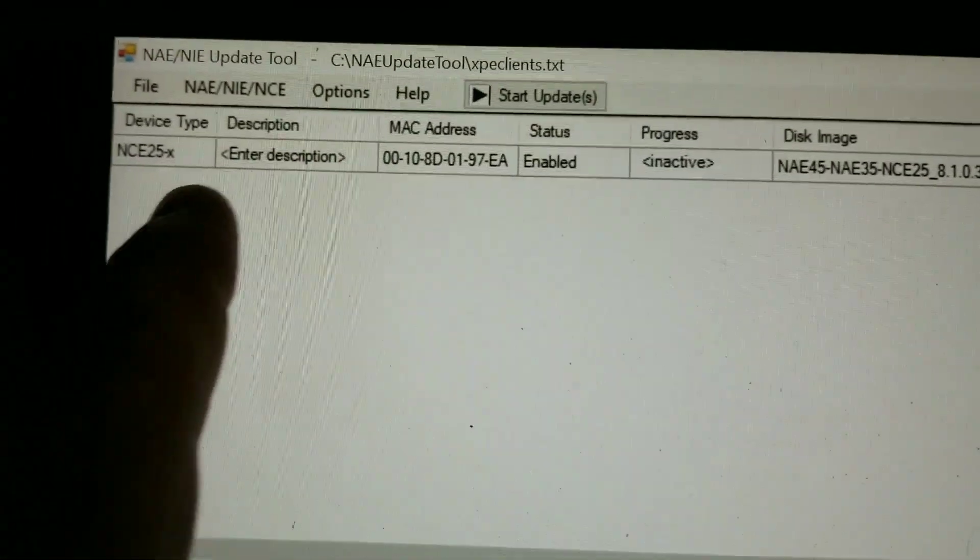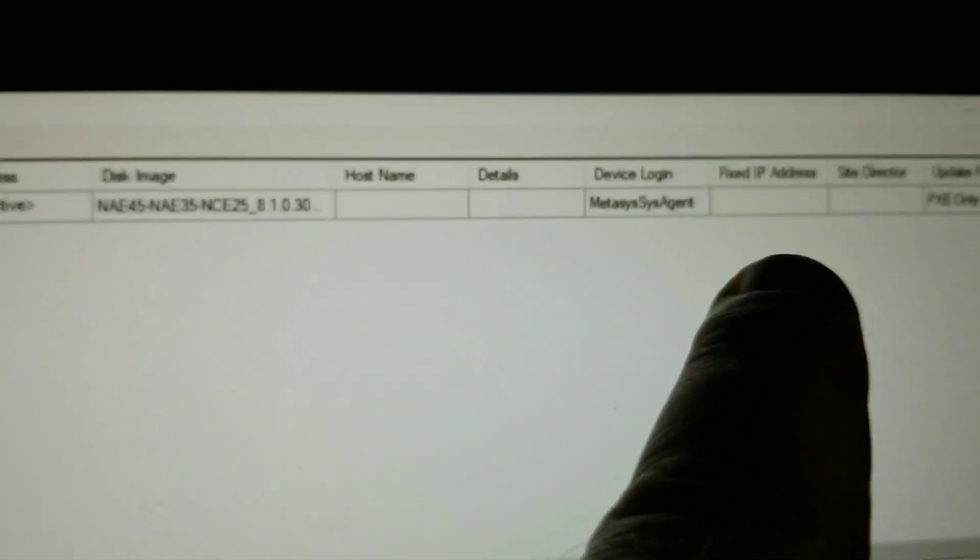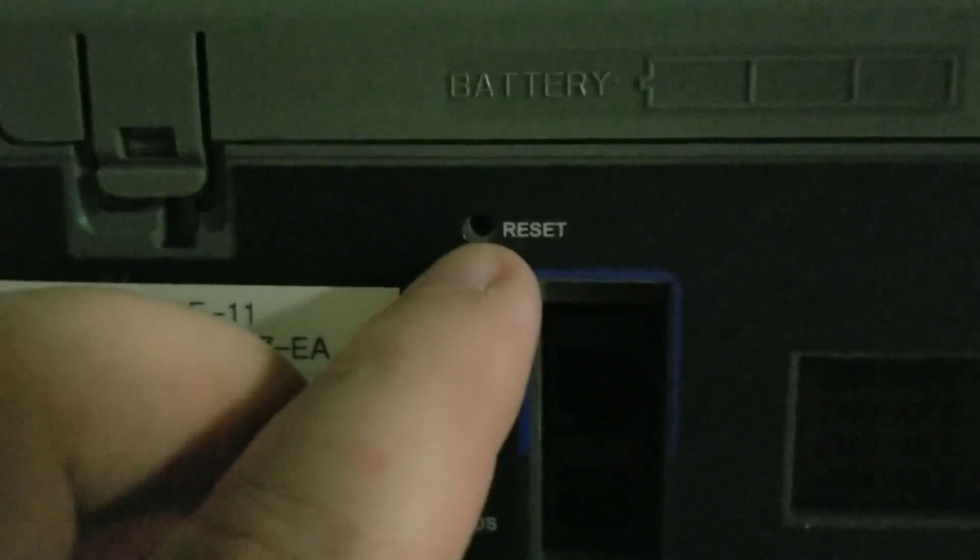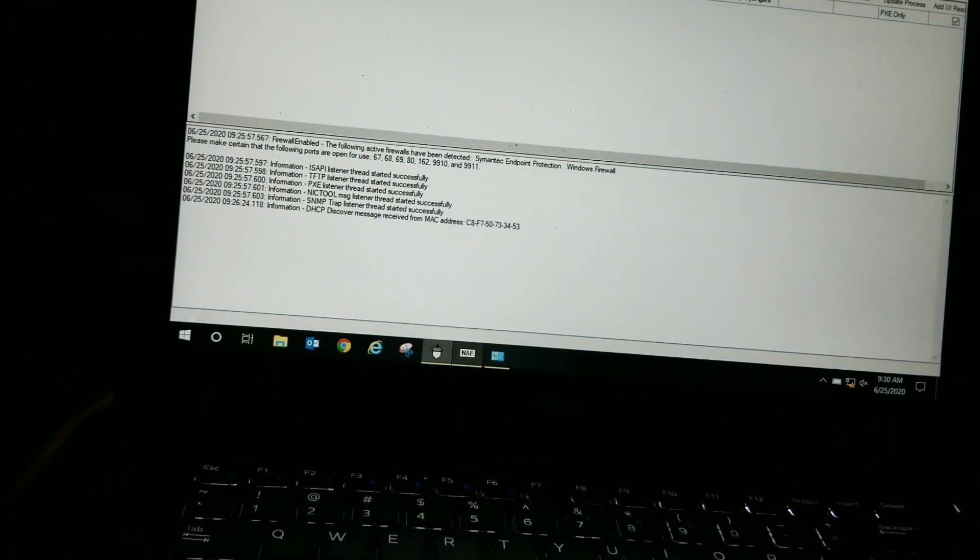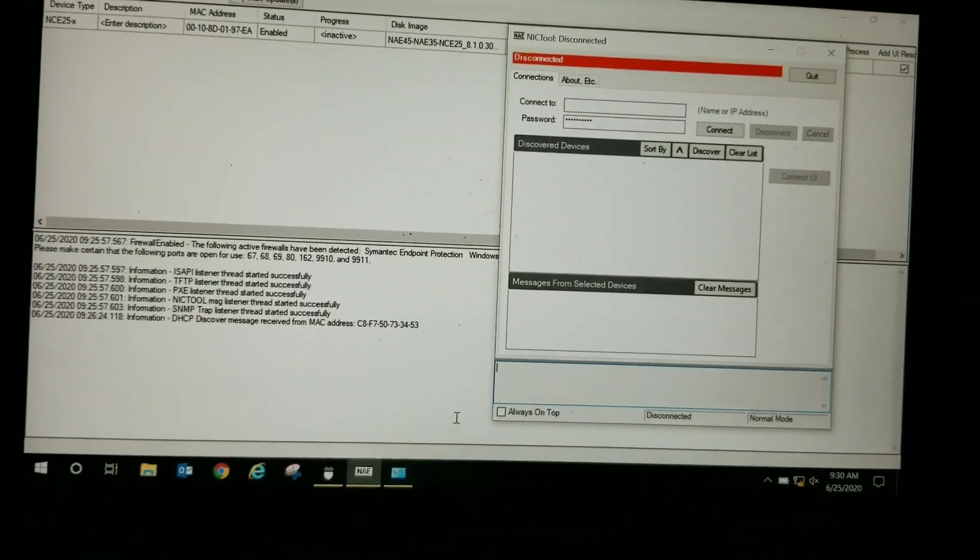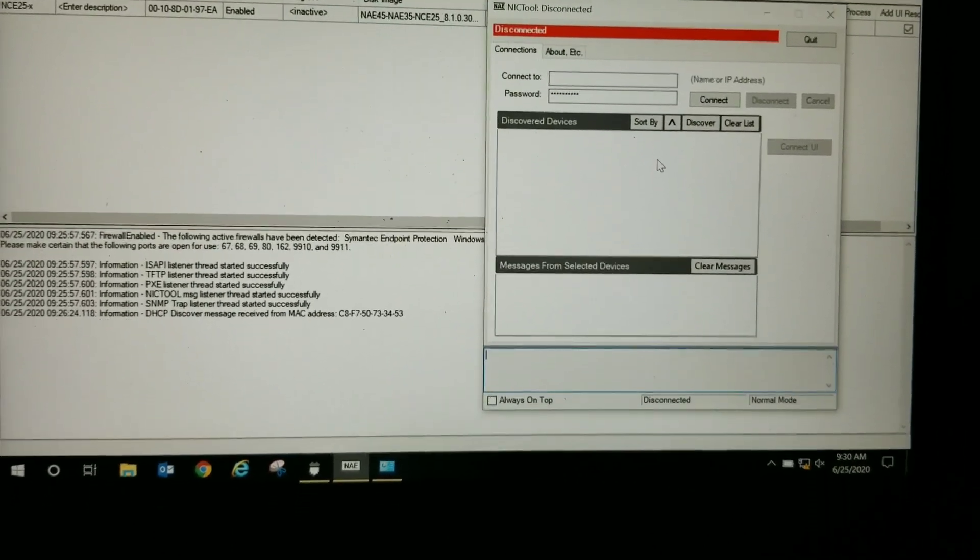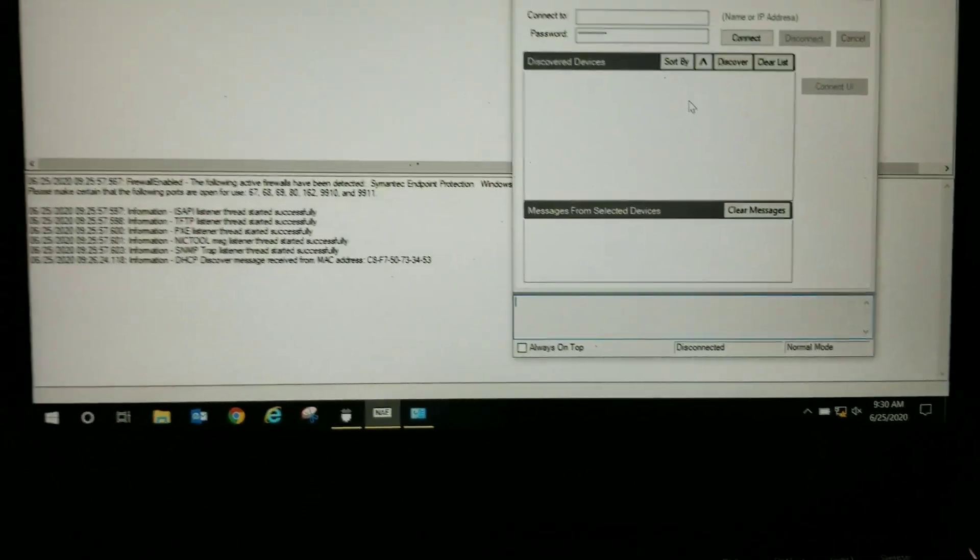What it's going to do here is it is going to populate this window with all of your information. From this point, what you will do is either cycle power on the device, or you can press this reset button. And once you do that, the update will automatically start when the device reboots and the run light comes on. You should see with your information tool, as it is rebooting, you will see the device populate in here with the address that it pulls and everything else.